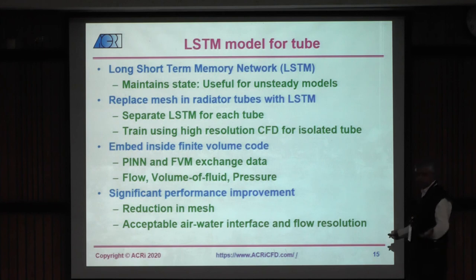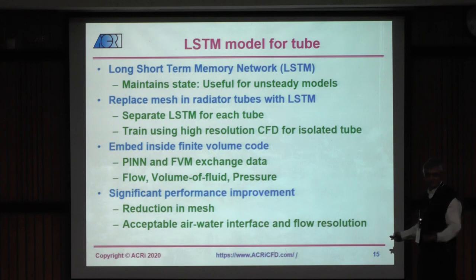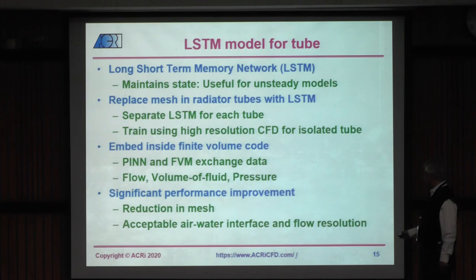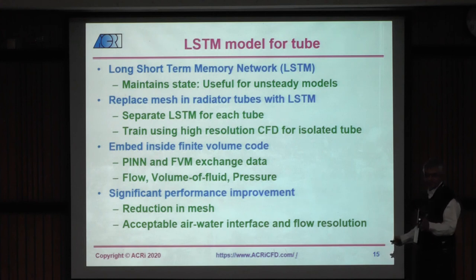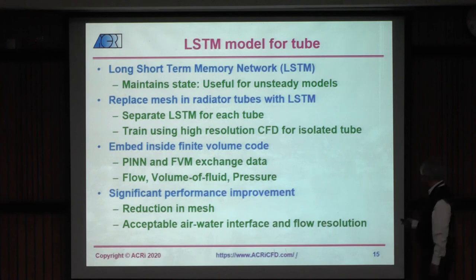By dropping all the mesh points inside the tubes, you save a lot of mesh points and get a significant improvement in speed. We also found that the air-water interface is a little bit diffused compared to finite volume, but since we just want to make sure there is no air sitting inside the tubes at the end of the process, we could live with that. It gave fairly good flow resolution.